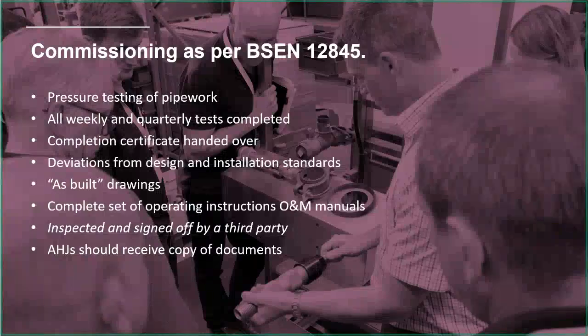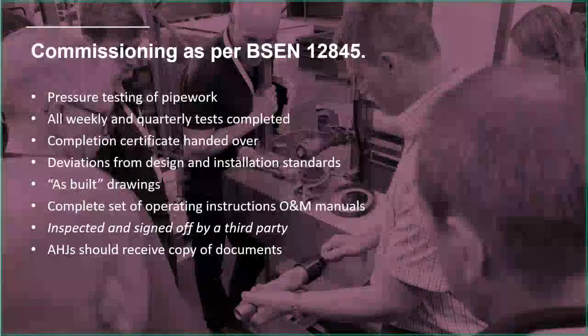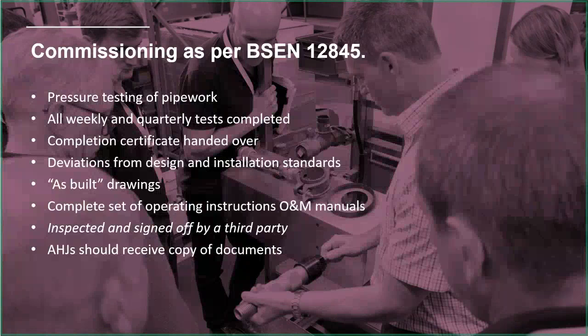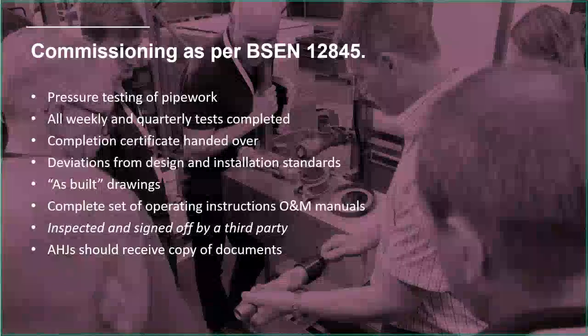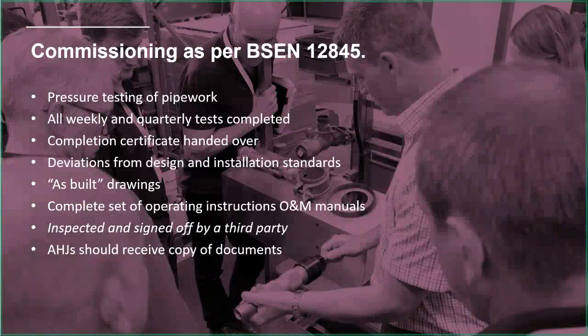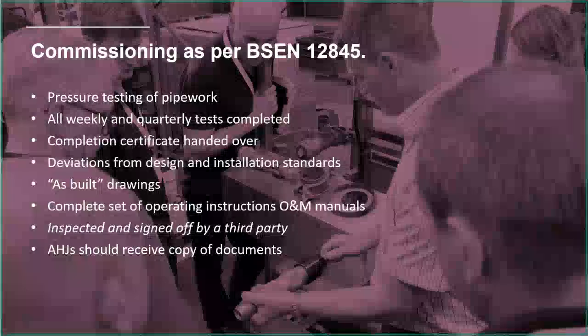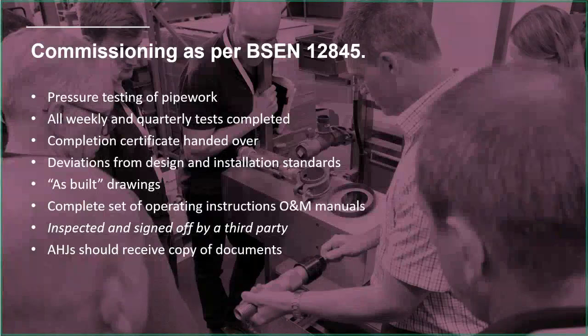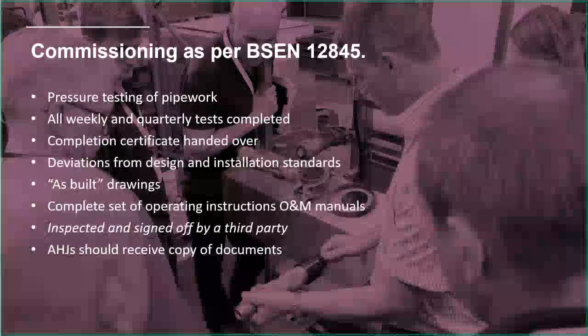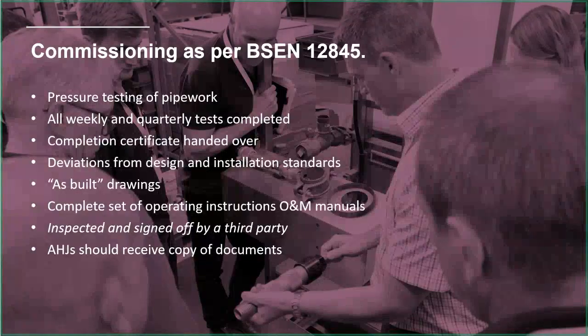Inspected and signed off by a third party. So I'll put that in italics. That is in the standard, but it uses some words that essentially mean if appropriate, if that's what's been agreed, then it needs to be signed off by a third party. Let's say generally it isn't. And quite rightly, the sprinkler contractor would say that if that's what you want, then you organise it and I'll cooperate. But it isn't something the sprinkler contractor is going to volunteer to do. As far as they're concerned, the work they've done is good. They're self-certifying it, they're signing it off. But if you want a third party to have a look at it, then that can be done. And then, the AHJ should receive a copy of documents. So that's a summary from 12845.